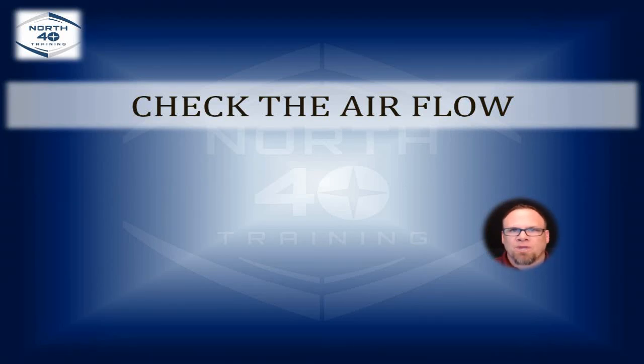Now we come to airflow. Airflow has to be one of the single most important yet overlooked parts of the heating or cooling system, no matter when they're being put in. And that's a shame. Guys like myself that have been in the industry for a long period of time, started clear back in the 90s or 80s or before, may have never actually had the proper teaching to learn how to check airflow, to properly learn how to use a blower performance chart or a manometer to aid in their diagnostics for airflow. We're going to talk about that right now because I place a fundamental core value on this subject.